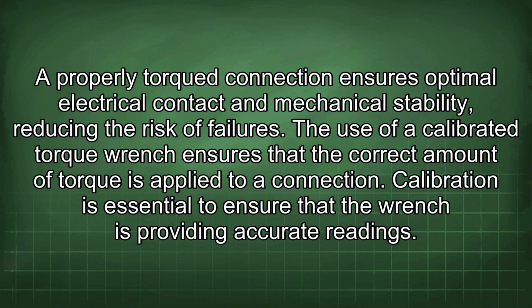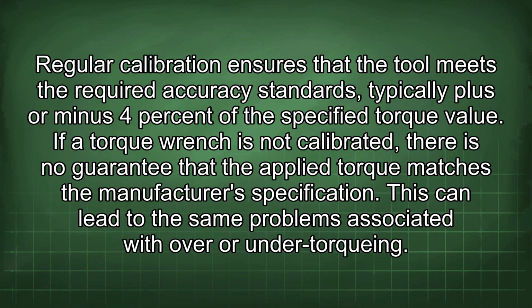The use of a calibrated torque wrench ensures that the correct amount of torque is applied to a connection. Calibration is essential to ensure that the wrench is providing accurate readings. Regular calibration ensures that the tool meets the required accuracy standards, typically plus or minus 4% of the specified torque value. If a torque wrench is not calibrated, there is no guarantee that the applied torque matches the manufacturer's specification. This can lead to the same problems associated with over- or under-torquing.